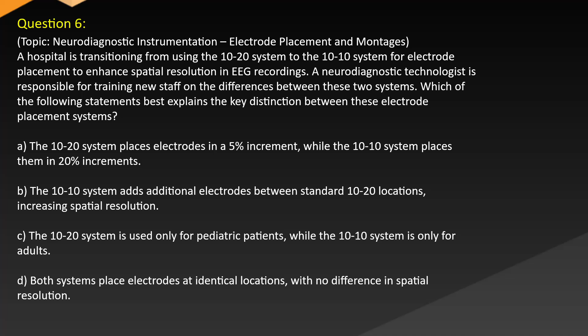Answer: B. The 10-10 system adds additional electrodes between standard 10-20 locations, increasing spatial resolution. Explanation: the 10-10 system is an extension of the 10-20 system, adding more electrodes for higher spatial resolution and better localization of epileptiform activity. Why B is correct: the 10-10 system increases the number of electrodes by placing additional electrodes halfway between standard 10-20 sites, enhancing precision.